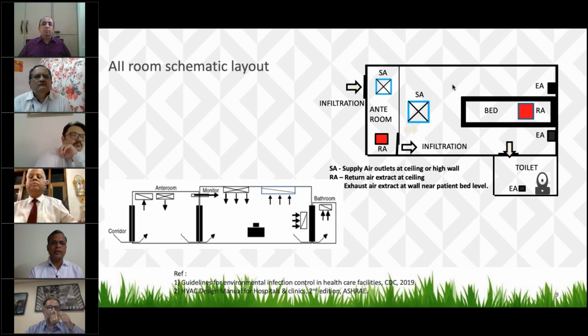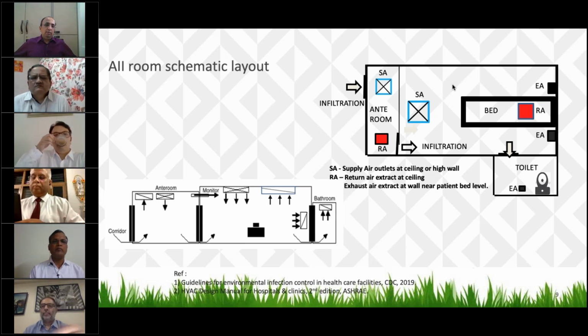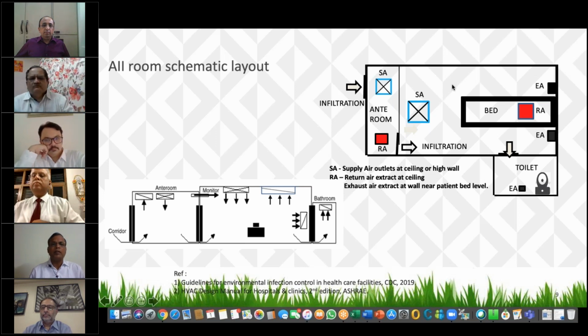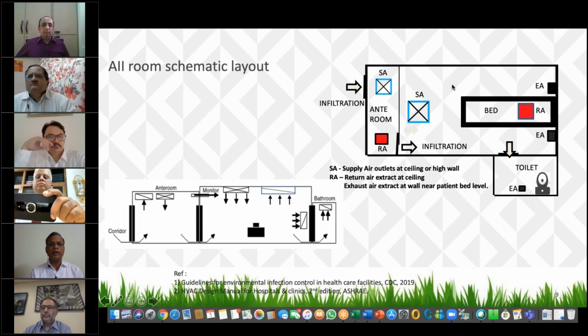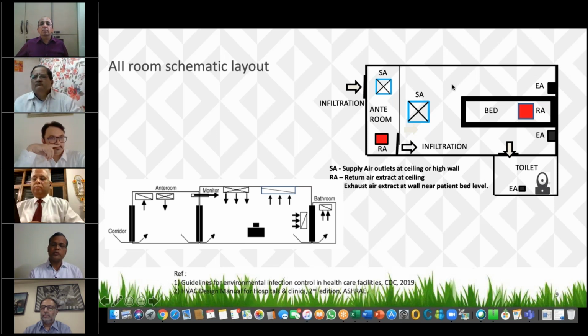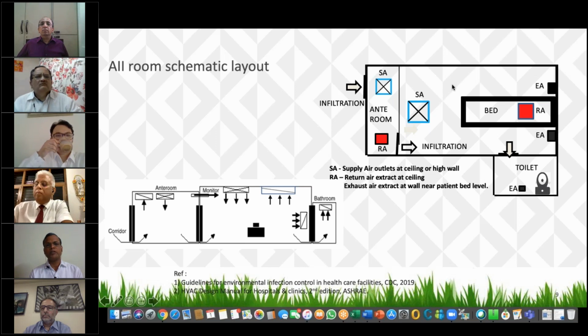So we are talking about a specific case like the COVID situation, and we are talking about an airborne infection isolation room, and the layout has been clearly laid down in the CDC guideline document for environmental infection control in healthcare facilities, 2019. The room where the COVID patient will have to be positioned would need an anteroom, which is typically a small room outside the main patient room. And the whole thing will have to be under negative pressure, which is called a cascade negative pressure. So from the corridor, the infiltration air will come into the anteroom, from the anteroom into the patient room, and from the patient room it gets exhausted outside. A part of it can be recirculated, but if it's recirculated, it is to be done through a HEPA filter, or the whole thing can be thrown out through an exhaust. And of course, the toilet exhaust will also happen.